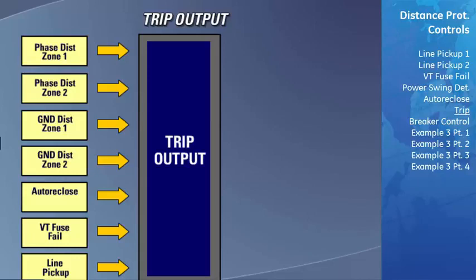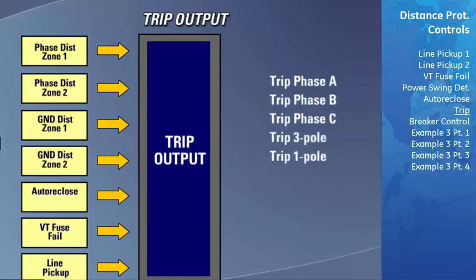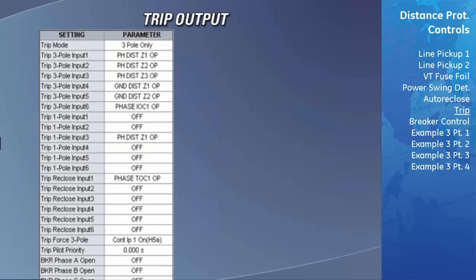Once the trip output has analyzed all of the logic, it produces several outputs that should then be assigned to trip the breaker. These outputs are trip phase A, trip phase B, trip phase C, trip 3-pole, and trip 1-pole. The trip output also gives an output signal that should be used to initiate the auto-reclosing sequence of the breaker. This output is labeled Trip Auto-Reclose Initiate 3-pole. We will now discuss all of the settings that need to be configured to make the trip output element operate correctly. If you wish to use the trip output feature, you need to select in the trip mode field either 3-pole or 3-pole and 1-pole.